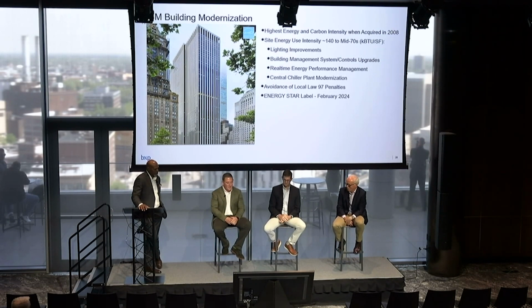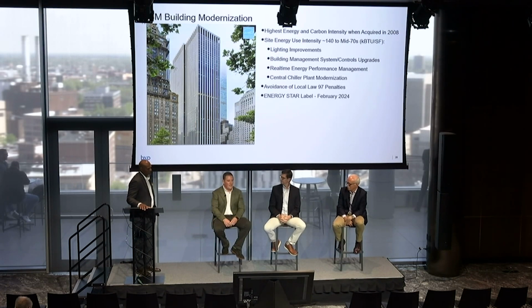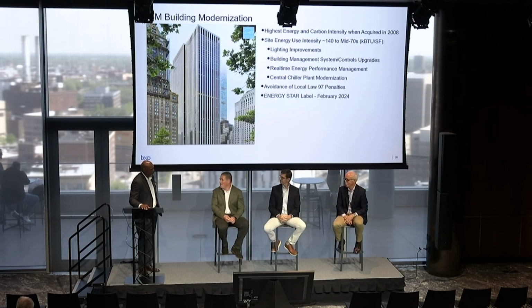We've been using real-time energy performance data, a combination of Measurabl and Nantum, to do more dynamic occupancy-based control of set points. We're doing more differential pressure set point adjustments, and much more setbacks in spaces that are underutilized. Think about the Monday-Friday occupancy patterns in office space. It's a tremendous opportunity that's not being leveraged right now across the sector, in part because of a deficiency of controls to do it well.